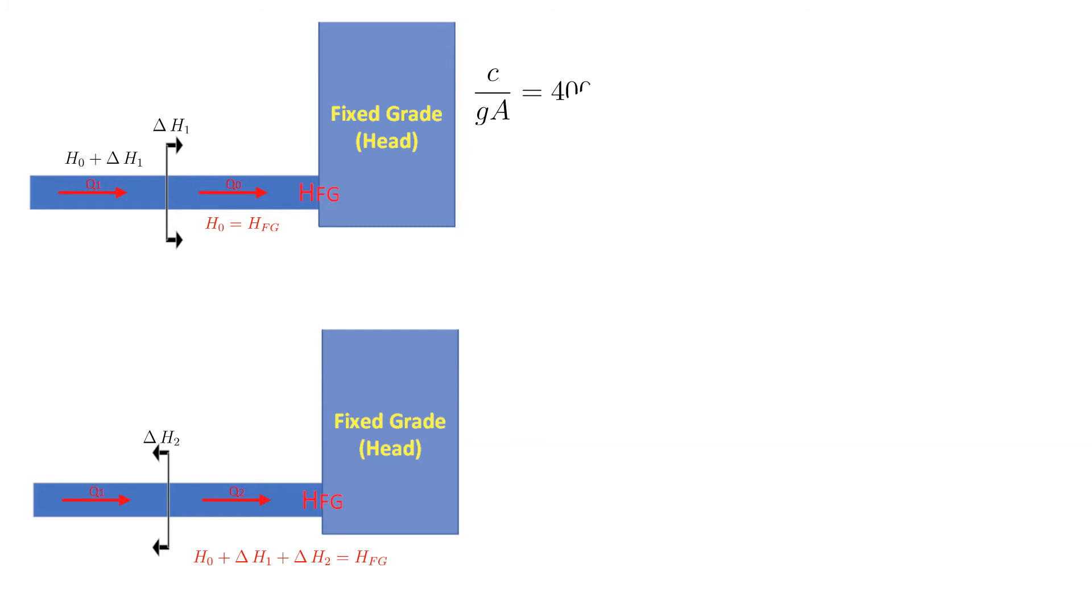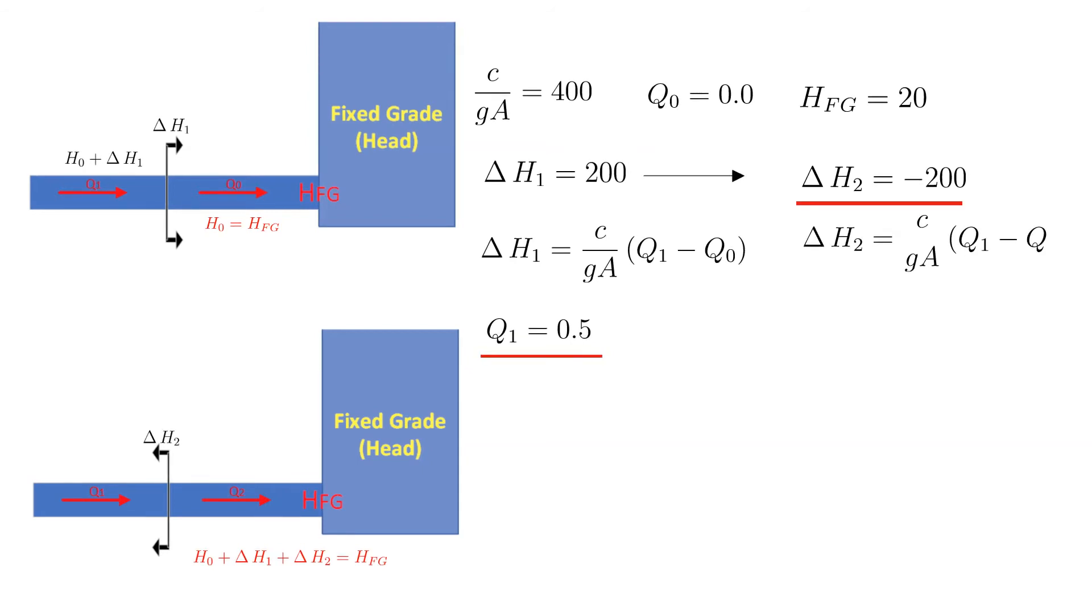Let's substitute in some numbers to add clarity. In this example the initial flow Q0 is 0, the fixed grade head is 20. The incoming wave is positive and has a magnitude of 200. The resulting flow behind the wave is 0.5. The wave reflects negatively off of the tank with a value of minus 200. The resulting velocity behind the reflected wave is 1.0.